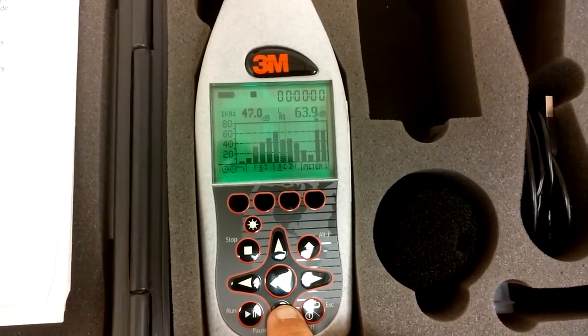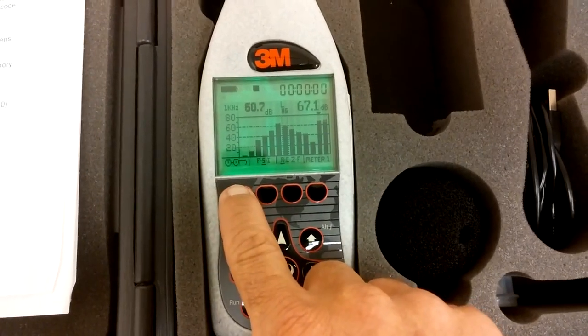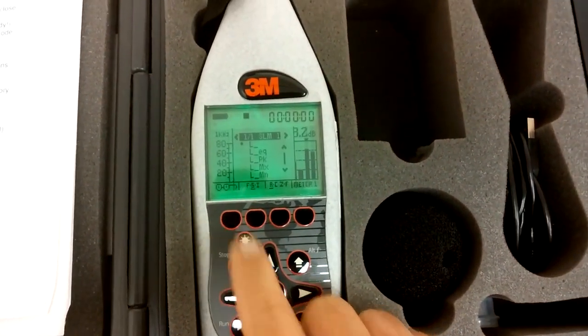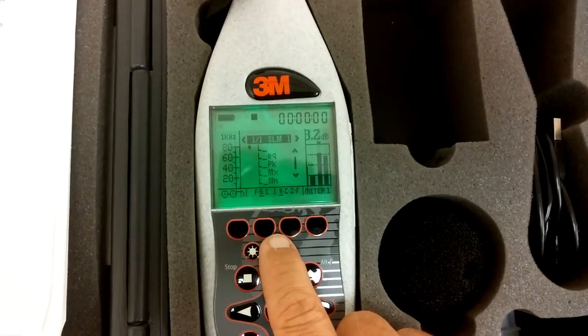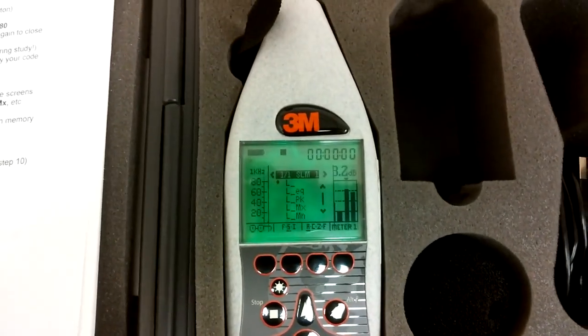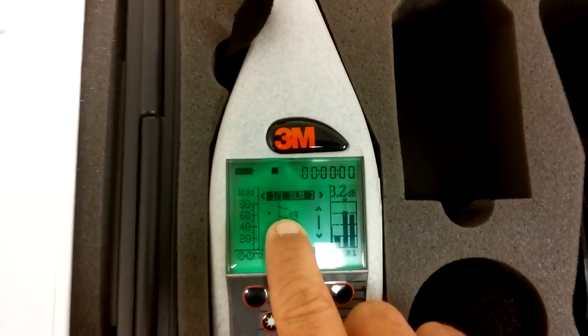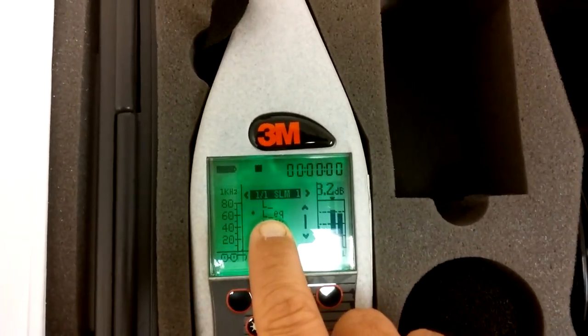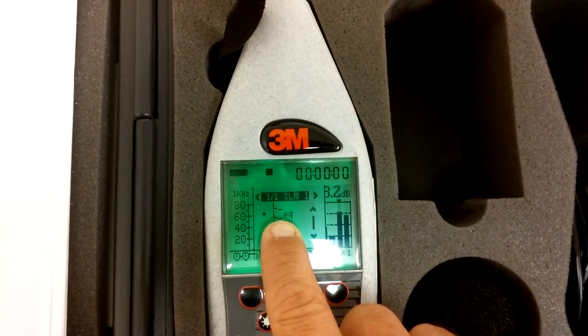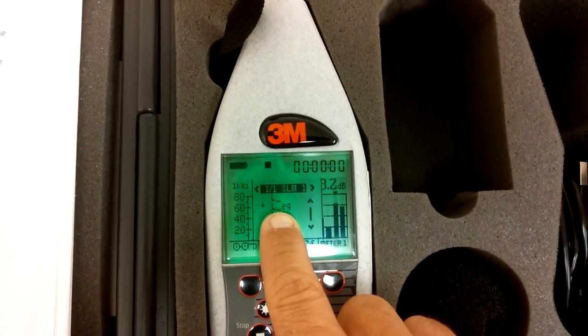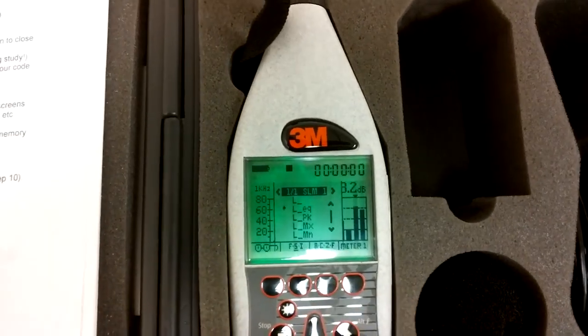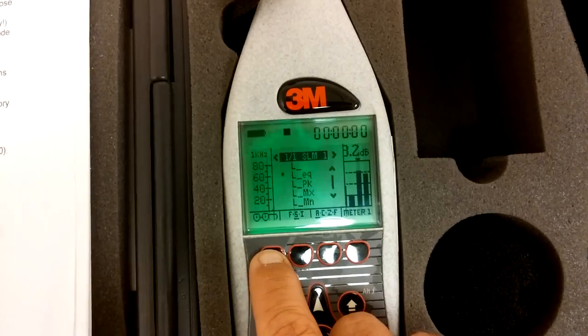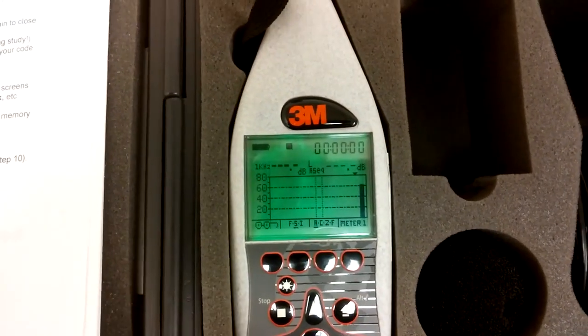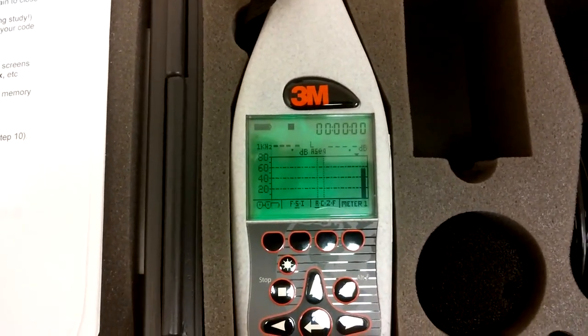So we're there. Using the glasses, sunglasses icon, click on that, and we want to arrow down to where it says LEQ. See right here, LEQ, that's the level equivalence. That's going to be like the mean or the average decibel level reading. That's what it's going to be measuring for. That's what we want to utilize. And once we get that, we'll hit the sunglasses again to make sure it's locked in.